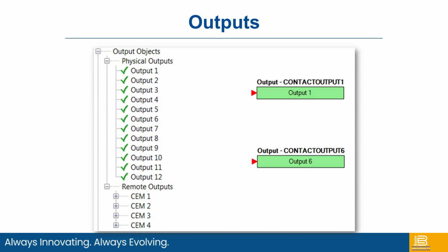Outputs are the same, so we've got physical outputs, and then as you can see on the screen, we've got remote outputs, so that's the contact expansion module. So you can not only drive the outputs on the hardware itself on the DGC, but you can drive any of the accessory modules that are connected as well through the logic.